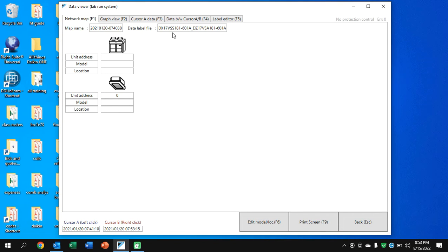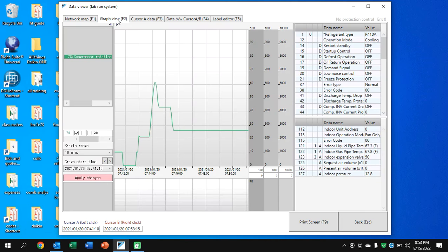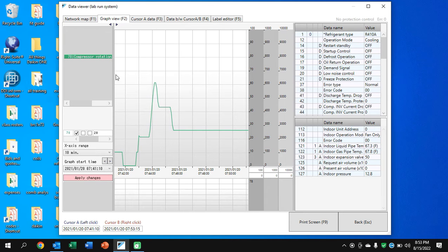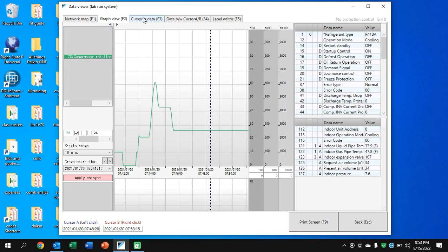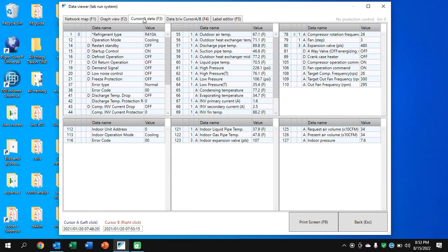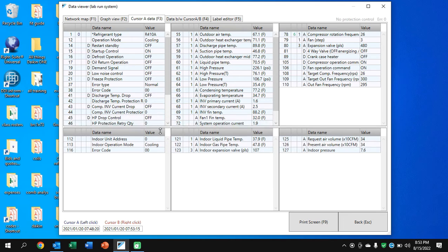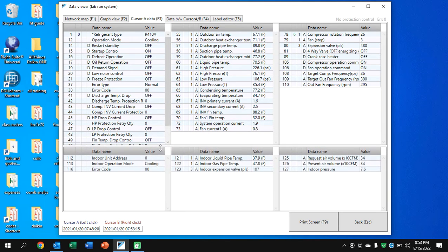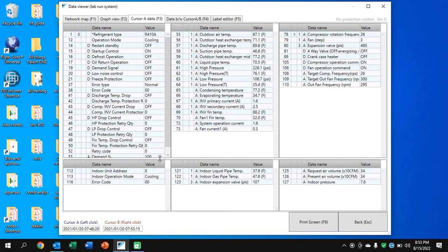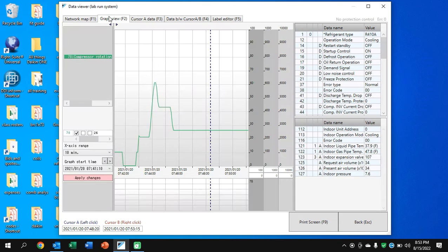Let's go look at my other lab units. I think I have a couple more here in a different application. And this would be DX17 as well. But this would be possibly with a gas furnace. And when we look, we'll see I'm monitoring the compressor in this case. We're going over the compressor rotations. And we can look at the data as well along that same timeline. And we can see what's occurring. And we'll see now when we go down below, we have a lot more data. We're using a gas furnace for the coils. We're pulling more data in the lower area. We're pulling in some pressures and temperatures that we'll see more often.